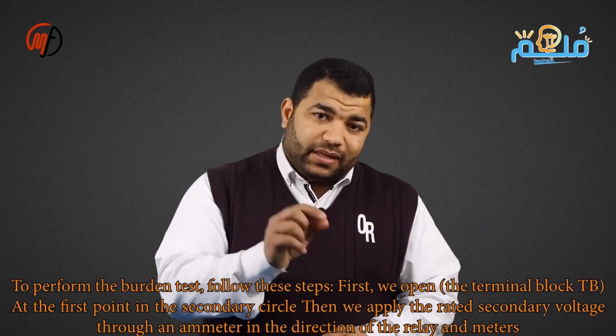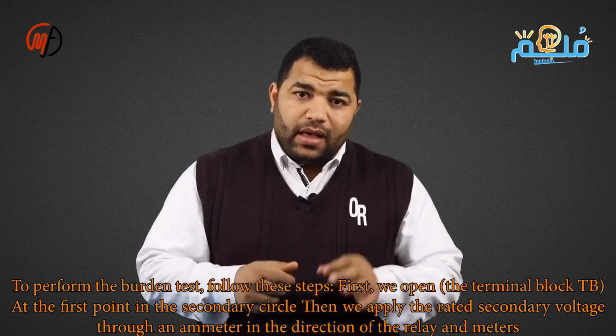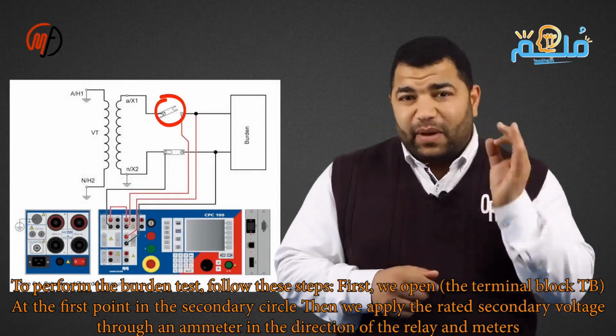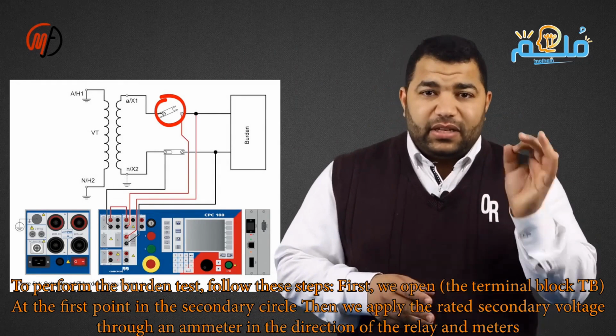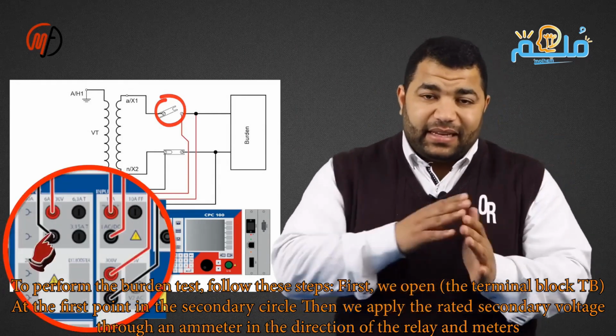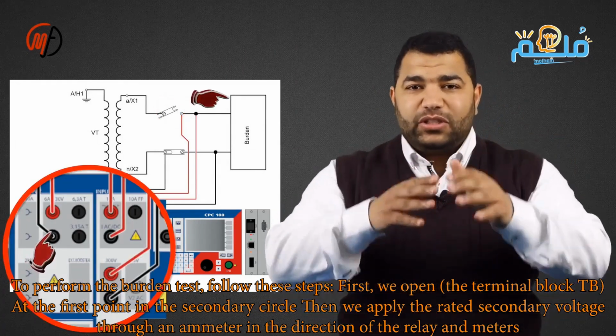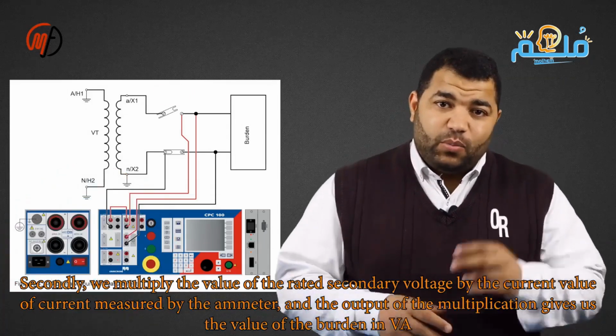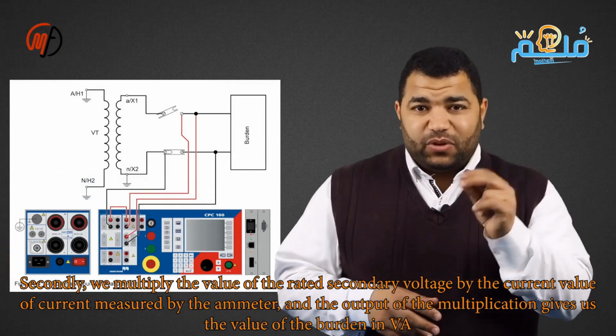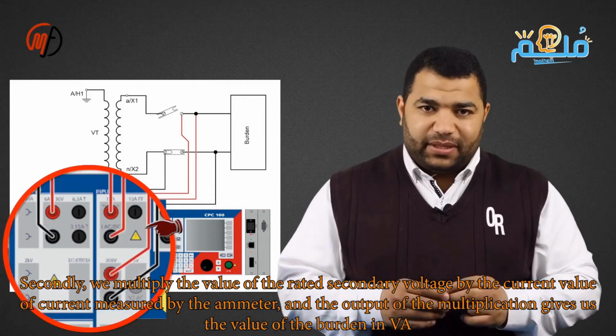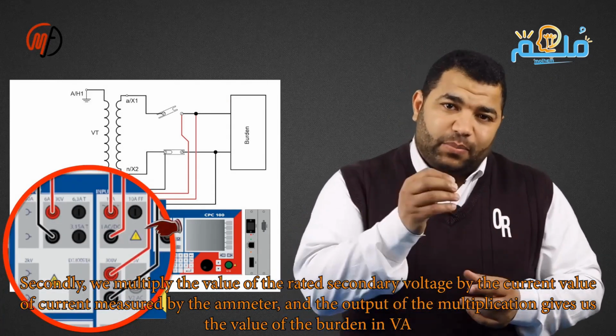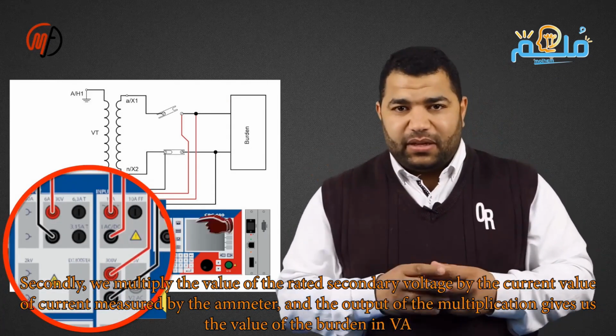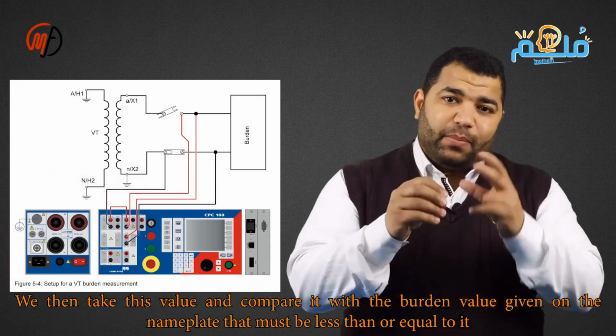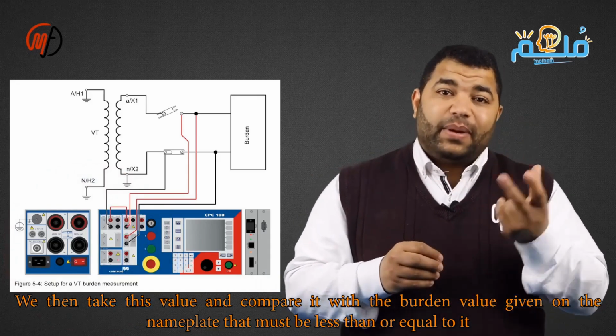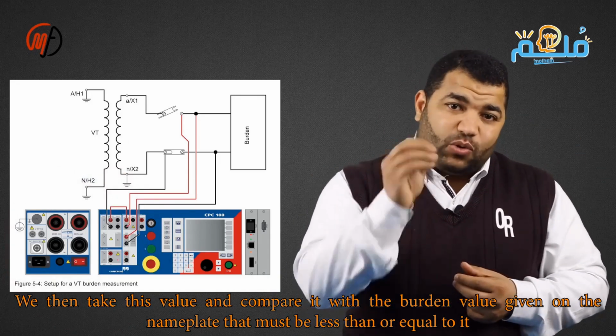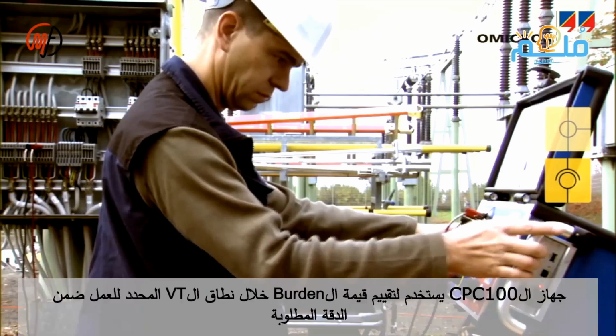To perform the burden test, we follow these steps. First, we open the terminal block at the first point in the secondary circuit, then we apply the rated secondary voltage through an ammeter towards the relay devices. Second, we multiply the rated secondary voltage by the value read from the ammeter, and the result gives us the burden value measured in volt amperes. We then take this value and compare it with the burden value on the nameplate, which should be less than or equal to it.